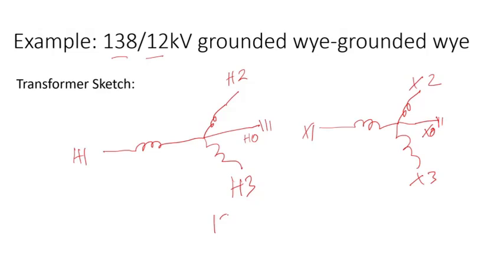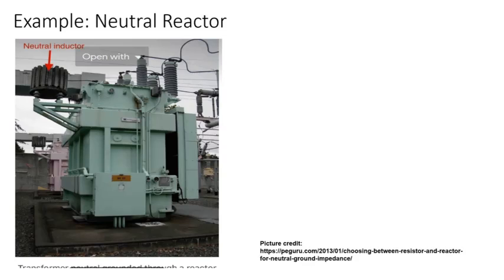The 138 kV side is the line-to-line voltage and 12 kV is the low side. Here's a picture from the internet showing a transformer with the neutral bushing grounded through a reactor or inductor. Some reactors might be mounted on the transformer, and others are standalone with a support that goes to a foundation, with the lead brought from the neutral.